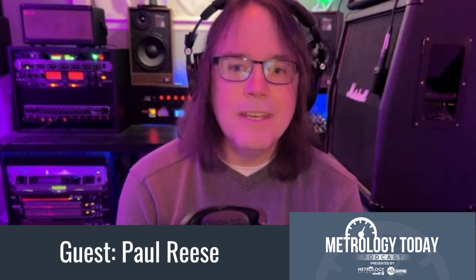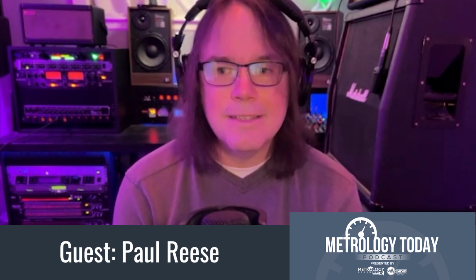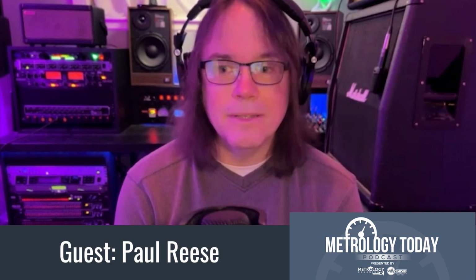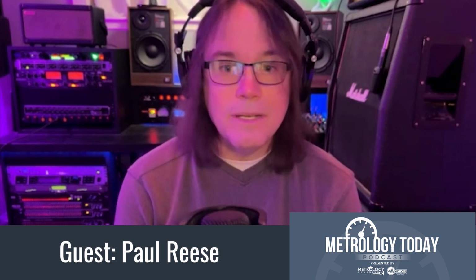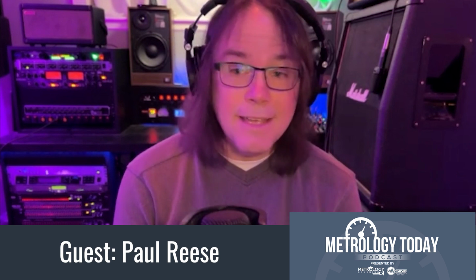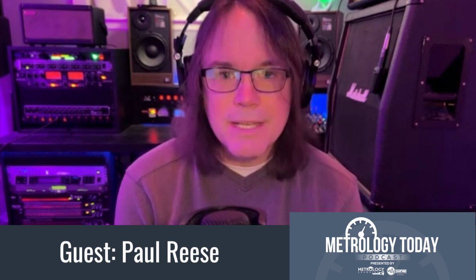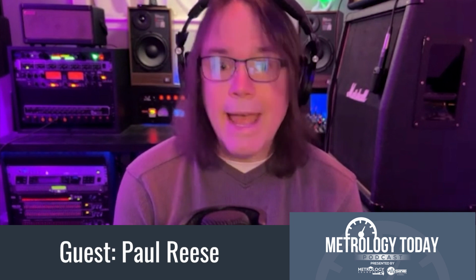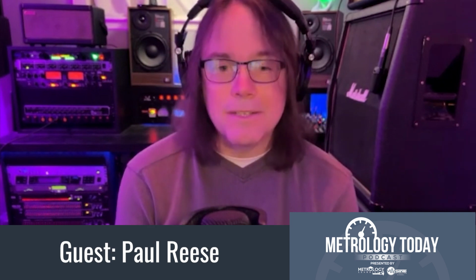And the advantage that overbuying gives you, and I'm not in the equipment manufacturing business, I'm just saying, is that as an engineer, if you overbuy and you buy an instrument that is way better than you need, you can always derate it and calibrate it to less accurate specifications. And then you have the advantage of knowing, well, a 3458 would meet 0.01% DC voltage. Its end of period reliability would be as close to 100% as you could probably get. And now you've overbought, the specs are good.